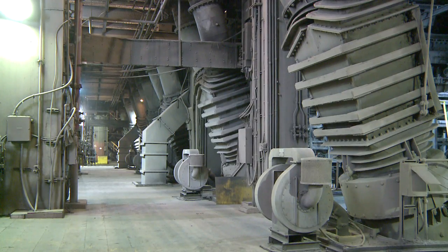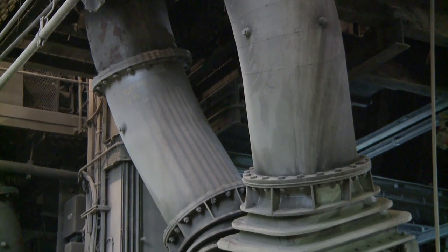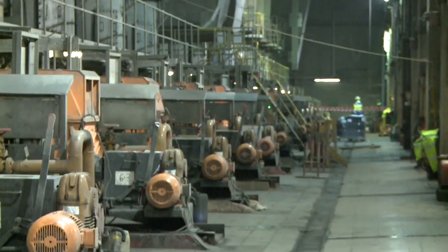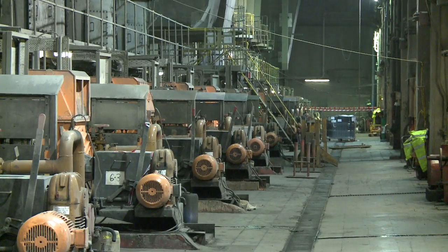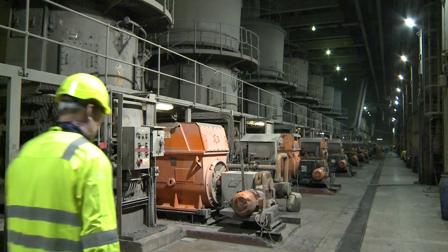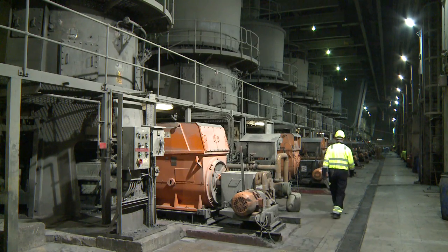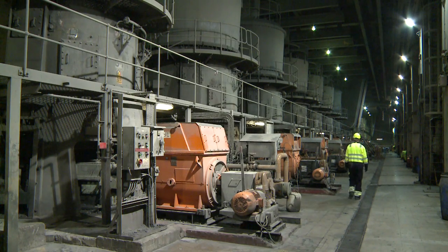When the coal goes straight up to the top of the boiler house — and this boiler house is about 200 feet high — the coal falls into bunkers down big chutes and is slotted into six big mills, because this coal is pretty poor stuff. You could never light it in a normal fire. So to burn it, it has to be ground to a very fine powder, ground to the consistency of face powder.